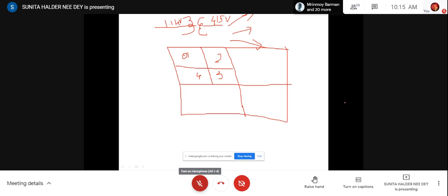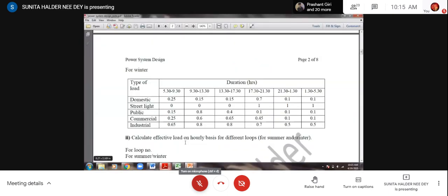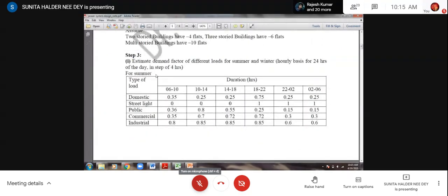So for that reason, now you see the note, your note. In the note, it is given to estimate the demand. Can you see my screen, the PDF? So estimate the demand factor of different loads for summer and winter. So why demand factor estimation is required, that I have told you. Now, say you are designing the distribution system electrically, but you are not consuming that. You will not supply that. So what you have designed should be conveyed to the power system operator also.